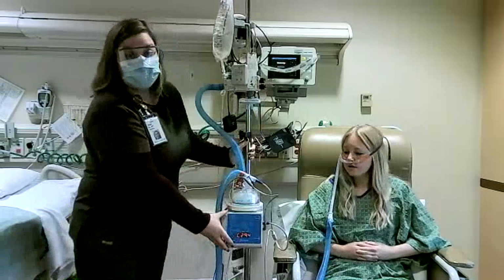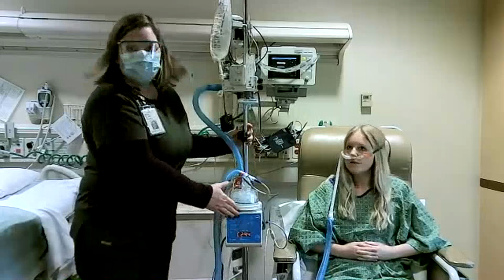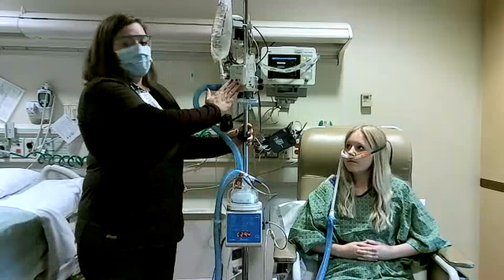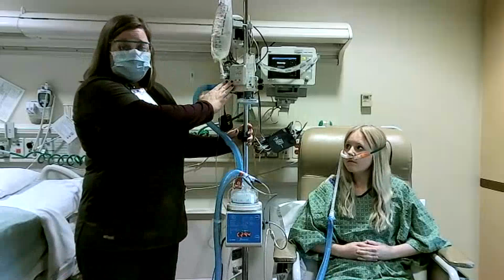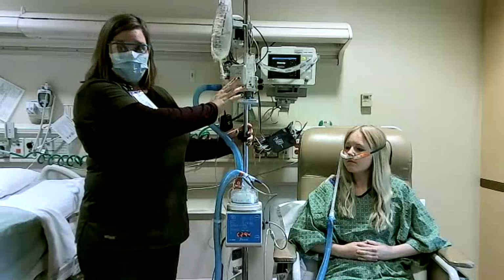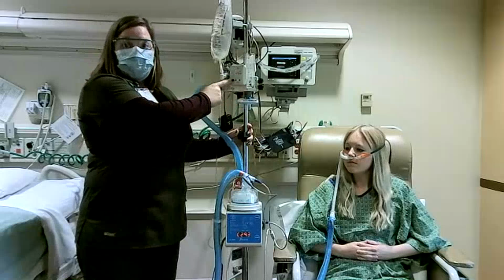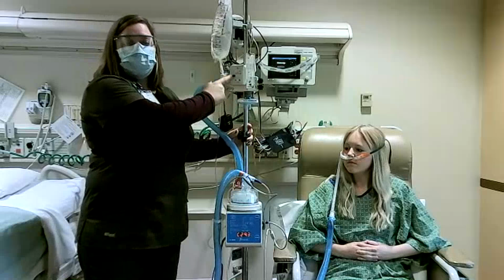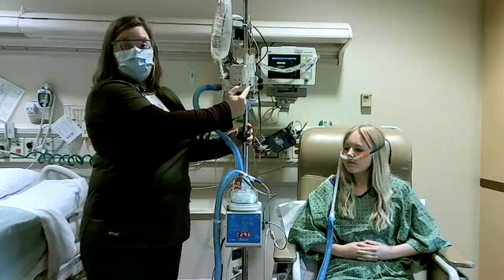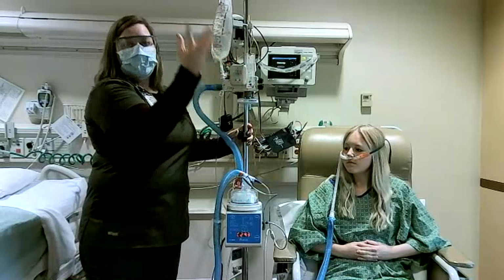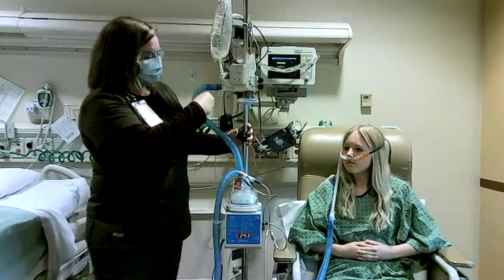So on this, you'll notice that there is a heater. This is the same heater that we use on a ventilator. And then there is an air and oxygen blender. With this, you get two things you can control. You get your FiO2, the amount of oxygen, you can control that, and you can control your flow, which is how fast it's being delivered to the patient.